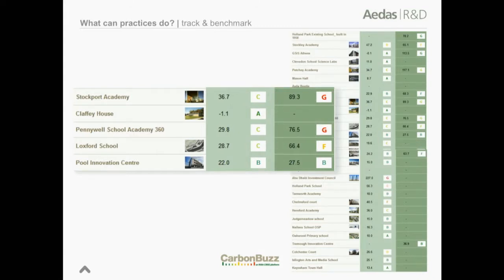What I found was kind of surprising. In the UK, the system is somewhat different than in the US. We have a system called energy performance certification, which relates to both design and operation. Our certificates for design stage are always A's, B's, and C's at worst. But when I went back to look at the operational rating, which is mandatory for all public buildings above 500 square meters, all the ratings came out D, E, F, G's, which is slightly worrying.